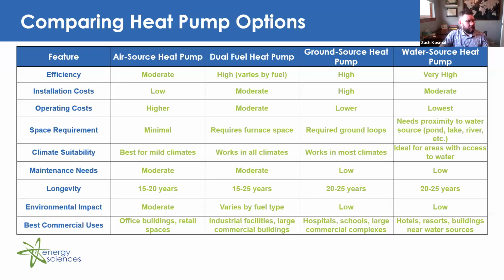And then lastly, space requirement for water source heat pumps. Typically, you need proximity to a water source, whether that be a pond, a lake, a well, or a groundwater source. But also you can have that cooling tower system or boiler system as your water heat transfer mechanism. So it kind of depends with water source heat pumps on the specific type of water source heat pump you're installing.